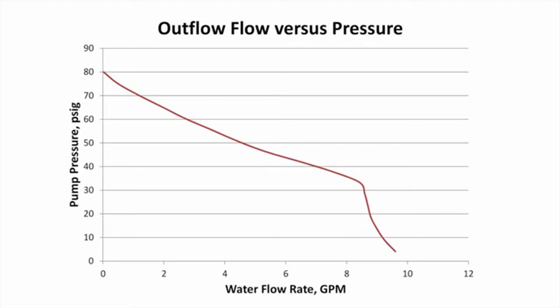All non-positive displacement pumps have a pressure versus flow curve that is very similar to this one. As the pressure decreases on the output of the pump, the flow rate coming out of the pump increases.